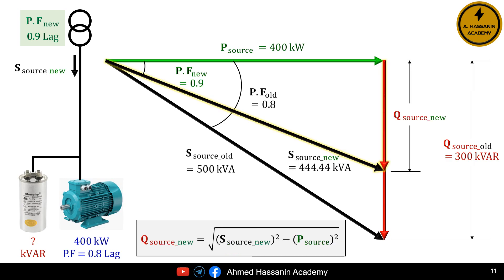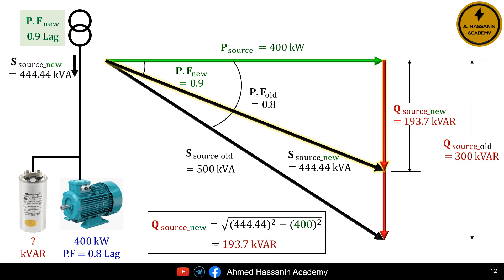Also, we can calculate the reactive power of the source after installing the capacitor, that is, after improving the power factor. Q source new is equal to the square root of (S source new)² minus (P source)², which equals the square root of (444.44 kVA)² minus (400 kW)², which equals 193.7 kilovars.